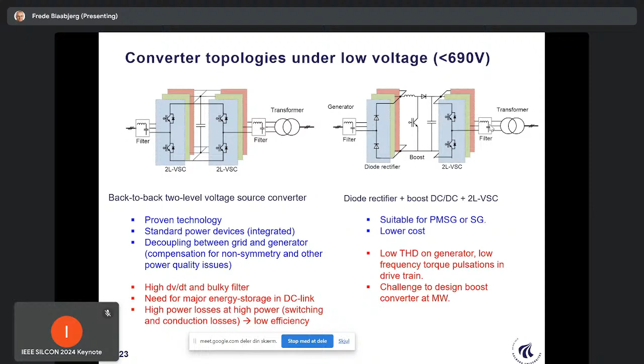In the case that the generator is a system where there is a back EMF, that is the permanent magnet synchronous generator or wound rotor synchronous generator, then voltage is generated here. Then we don't necessarily need an active converter on the generator side, but we need an active converter on the grid side. But the power is high, so we cannot just do it with one converter. So we built it in stacks, as you can see illustrated here. Here is maybe a stack of 2 megawatt. And then in order to do 10 megawatt, we put 5 of them in parallel, like illustrated here. This gives redundancy, right? If one fails, we can still operate.